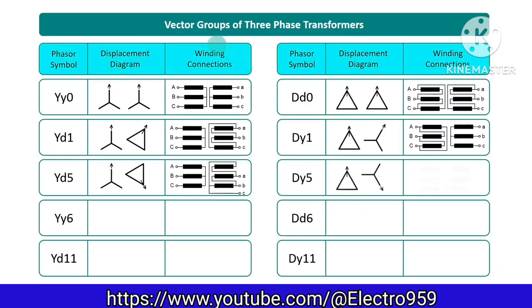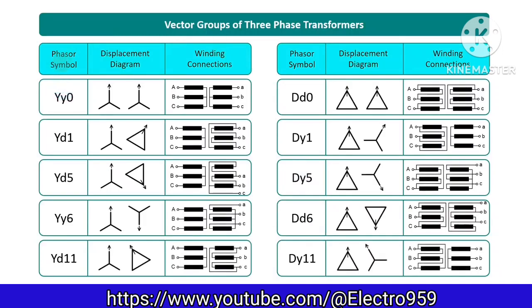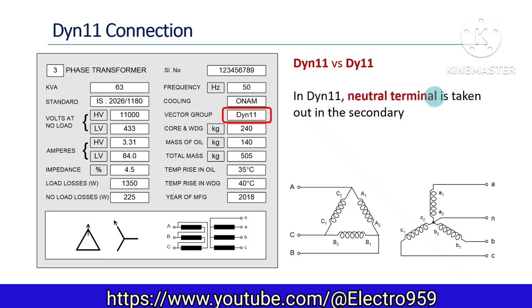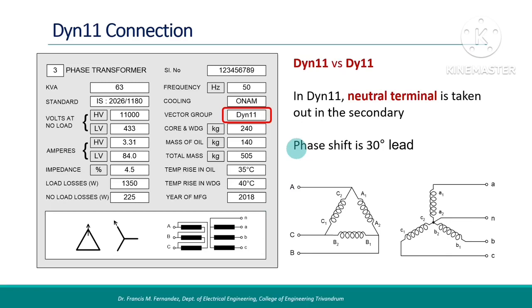Here we have a summary of all the vector groups discussed. The phasor symbol, displacement diagram, and connections in each case are shown. Going back to the transformer nameplate seen earlier, the vector group is given as dyn11. The difference from DY11 is that it has the neutral point of the secondary brought out as a terminal, and the connection diagram is changed accordingly — the neutral point is added. All other things, including the phase shift, remain the same. This gives an idea of what vector groups are in three-phase transformers.